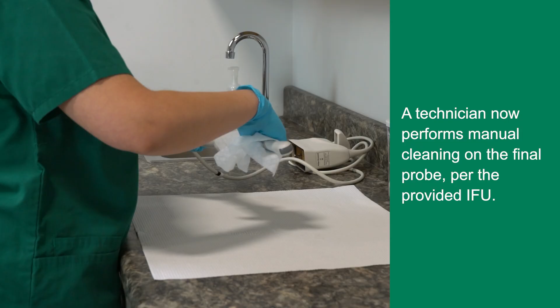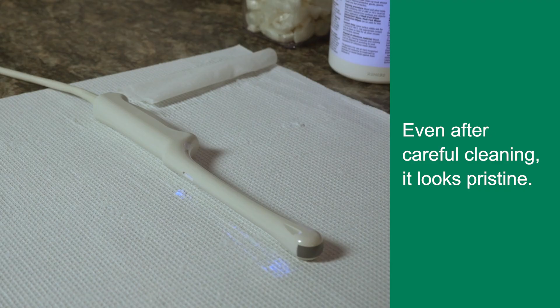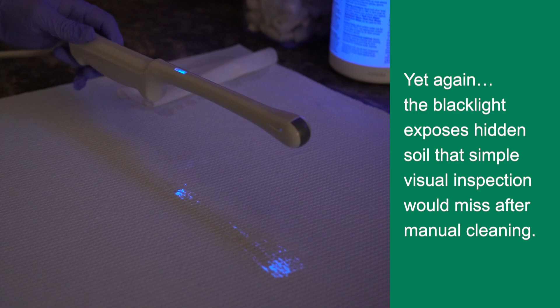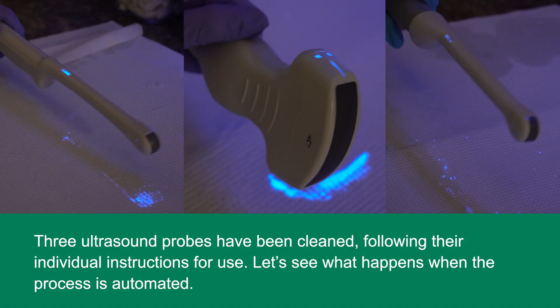A technician now performs manual cleaning on the final probe per the provided IFU. Even after careful cleaning, it looks pristine. Yet again, black light exposes hidden soil that simple visual inspection would miss after manual cleaning. Three ultrasound probes have been cleaned following their individual instructions for use. Let's see what happens when the process is automated.